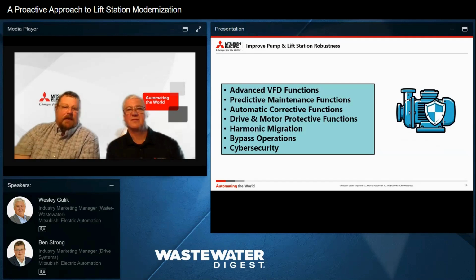Drive and motor protective functions, that's definitely something we can do with the VFD. Harmonic mitigation, that's something we have to consider as we're operating our lift stations with VFDs, if we choose to go that way. And bypass operations: if the VFD doesn't work, do I want a contactor bypass or a soft start bypass? How redundant, how reliable, how do I want to make my lift station operate?